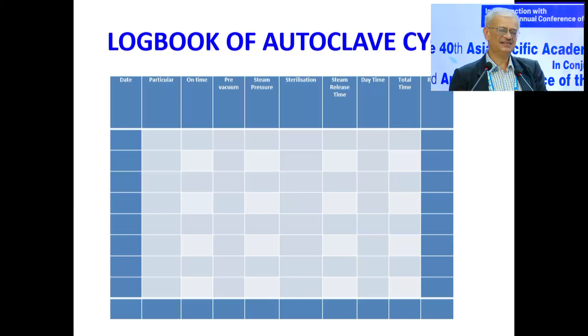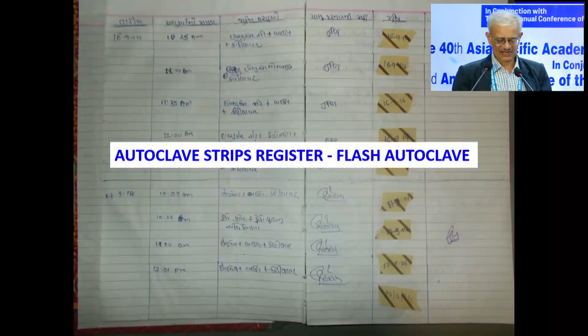This is the autoclave strips registers that we maintain. 3 things here. The strip color must be jet black, because it indicates only that the temperature has been reached. So if the color is not jet black, believe that the temperature was not achieved. This needs to be signed by the theatre in charge and by the surgeon both, and both of them are certifying that the color of the indicator strip was jet black. Similar register can be maintained for fast autoclave, the flash one, for ethylene oxide gas sterilizers also.